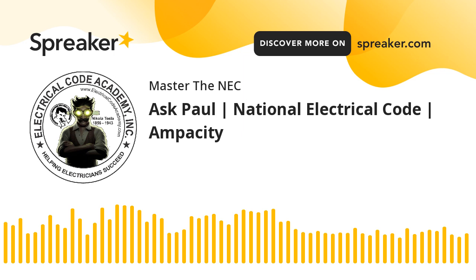Now, interesting thing about branch circuits is the ampacities. If you haven't done a lesson or seen my Derating Demystified video, of course you can't get it unless you're an annual subscriber. But in the Derating Demystified video, we talk about the fact that when it comes to a branch circuit, if I've got continuous loads, then I have to size the conductor and use 210.19(A)(1)(a). If I don't have any adjustment or corrections, what are they?